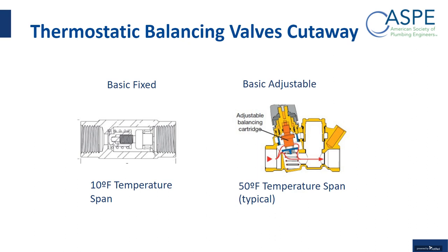The adjustable has a lot of the same components, but it has additional components because it also allows you to basically adjust the position of the actuator. And by adjusting the position of the actuator, that in effect is adjusting your return temperature, your control point. And so the fixed operates, can't be adjusted, operates over a 10-degree span from open to close, and the adjustable operates over a 50-degree span.